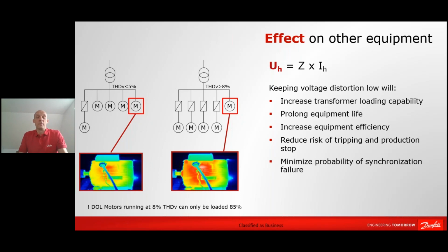So the effect of harmonic voltage distortion is not necessarily something you will see instantaneously, but something you will see over the lifetime. You will see reduced lifetime of your equipment. You will see risk of bearing stress. You will see risk of winding insulation issues in the motor and so forth. And that's the reason why it's essential that you try to reduce the voltage distortion in your installation.